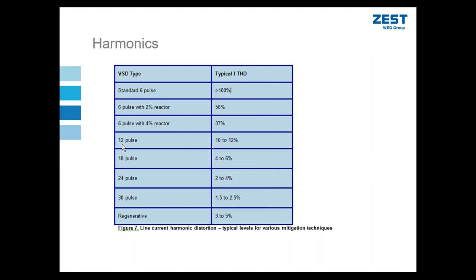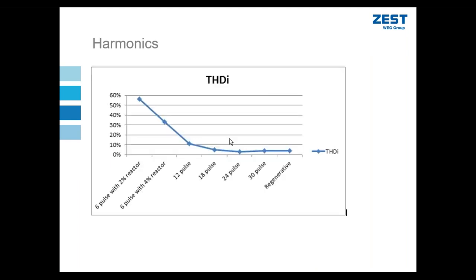Then if I introduce a phase shift technique and use a 12 pulse, I can get a dramatic improvement from 37% right down to between 10 and 12%. At 18 pulse, 4 to 6%, 24 pulse, 2 to 4%, 30 pulse, 1.5 to 2.5%. And I've just added a regenerative drive there just to compare. If I don't use a phase shifting technique, but I use an active front end drive, I will get between 3 to 5%. What we can see is that the improvement in harmonics as we increase the complexity of the number of pulses starts to wear thin after a certain point.